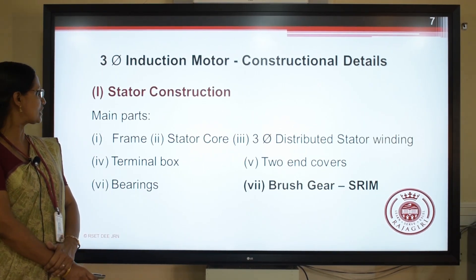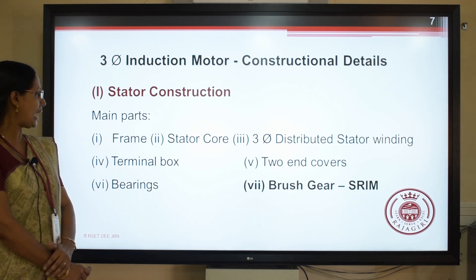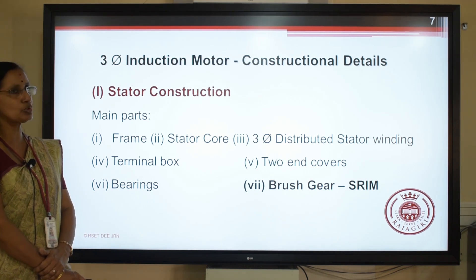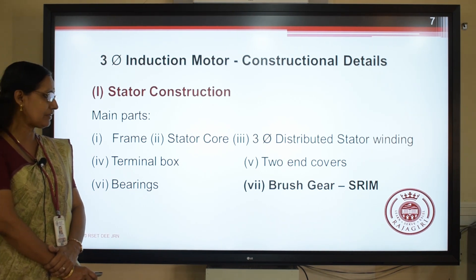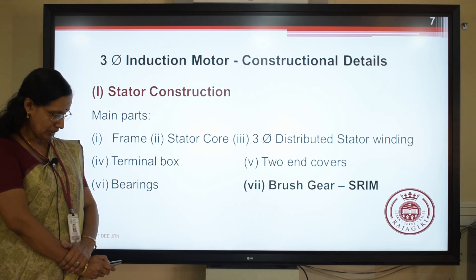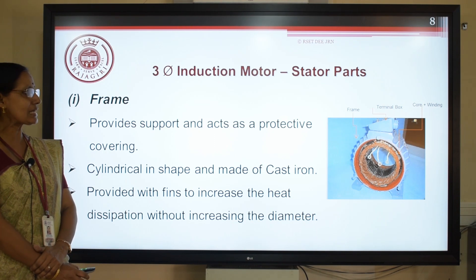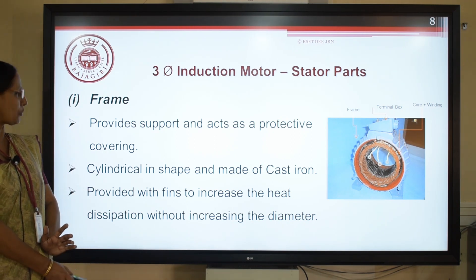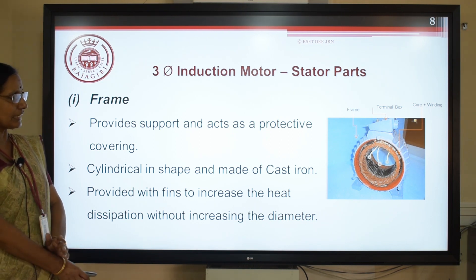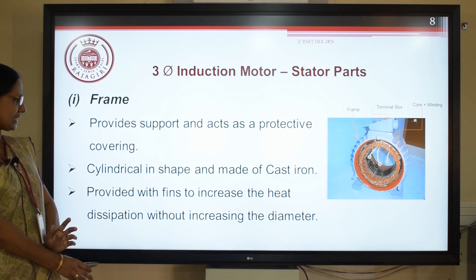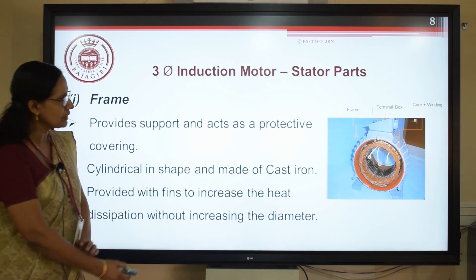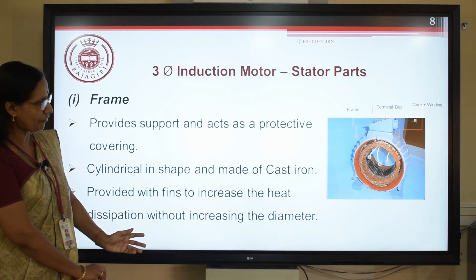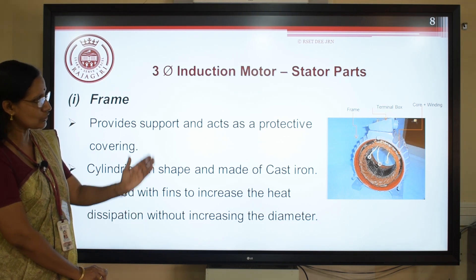Moving on to stator construction. The main parts are: a frame, followed by the stator core, three-phase stator winding, a terminal box, two end covers, bearings, as well as brush gear which is applicable only for slip ring induction motor. The frame acts as an outer covering — it provides support and acts as a protective cover. It is cylindrical in shape. Fins are provided to increase heat dissipation without increasing the diameter. You can also see the terminal box. This represents the stator with the frame, stator core, three-phase winding, as well as the terminal box.